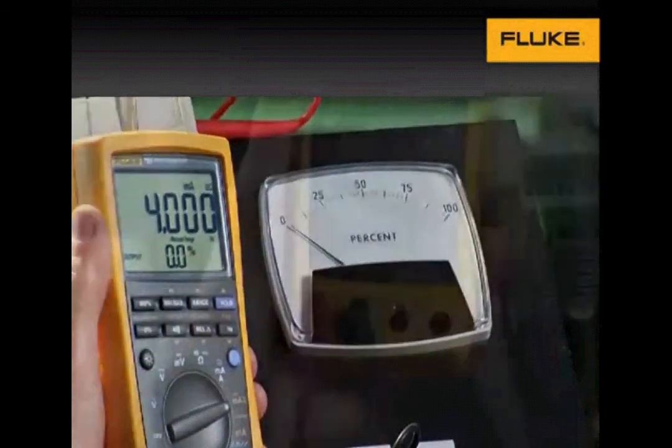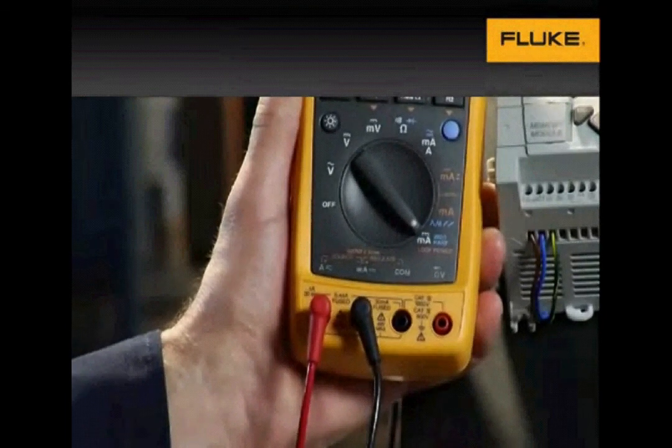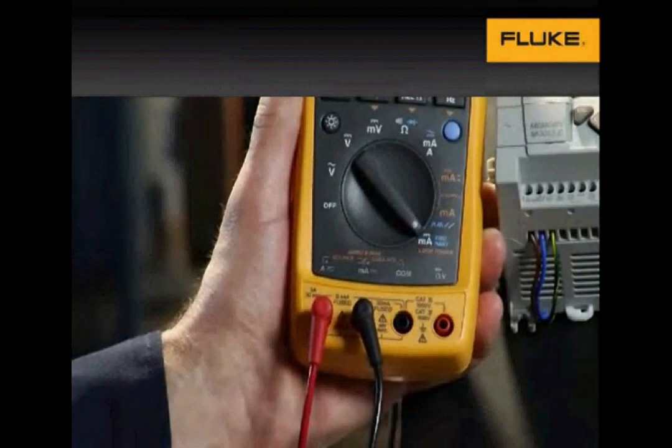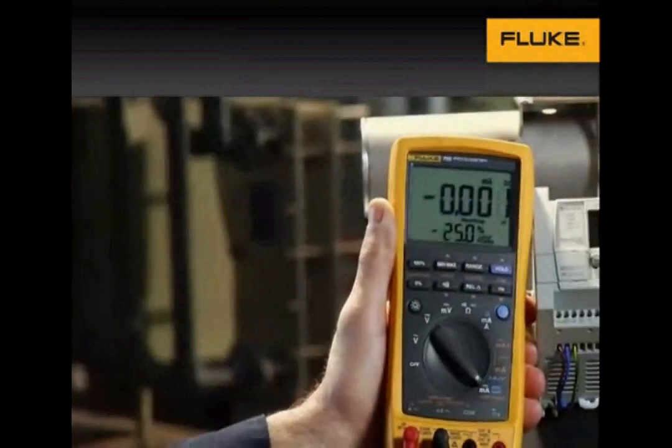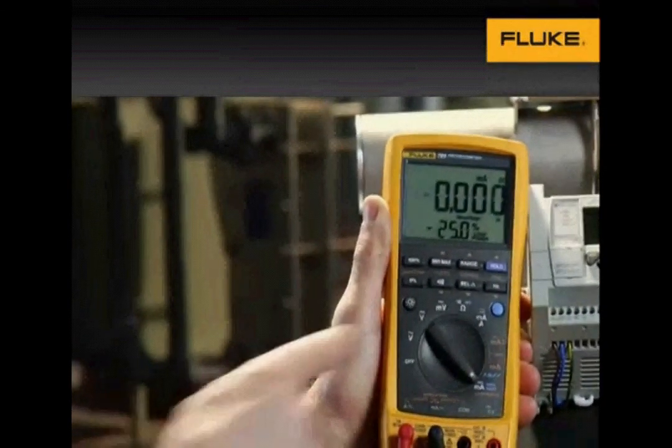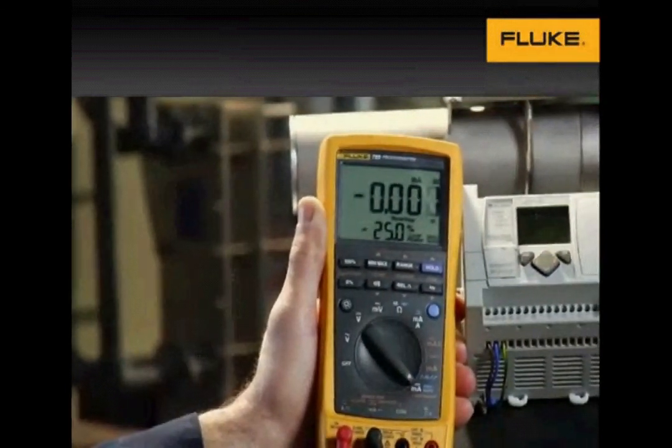The 789 also has a 24-volt loop power supply that will power a transmitter. You can simultaneously measure the milliamp signal drawn against the loop power supply. It also has a 250-ohm HART resistor you can switch in that will permit communication with a HART communicator.